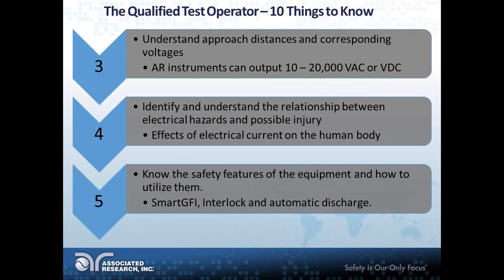We have an interlock built into ours as well. Most hipot testers have them, an interlock, which basically means if that interlock is not in place, the unit will not output voltage. And we'll get more into detail on that in a little bit, talking about the interlock. Automatic discharge circuits. Our units have auto discharge circuits built into every one, which means once the test is done, it's going to discharge the device under test so that if somebody walks up and touches the unit, they're not going to get hit because it was charged up. But there's a couple points to remember about discharging that I will get into in a moment here.